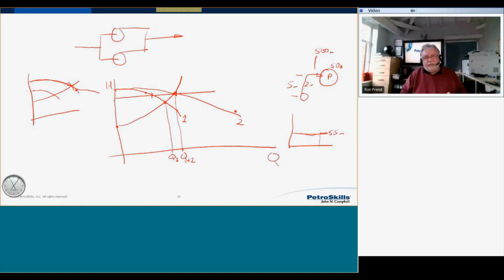As the discharge valve is fully closed, you've got no flow going through the pump, but you still need some power to keep this thing running. So you've got a couple of things going on there. First of all, you've got a lot of turbulence inside that pump. And don't forget, you've got all the mechanical issues. You're heating up the liquid. You're operating at very low efficiencies. So the calculation that we showed is good for most of the curve, but it tends not to work when you get to very low flows.